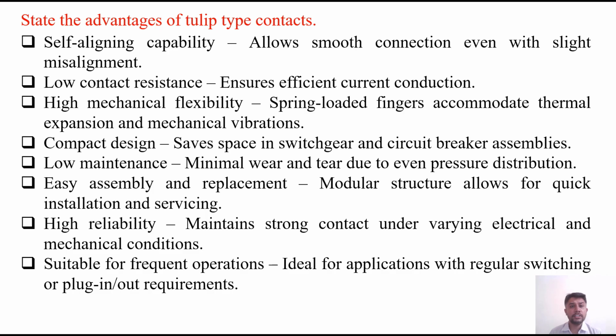State the advantages of tulip type contacts. There are several advantages of tulip type contacts, some of which are listed here. First is self-aligning capability. It allows smooth connection even with slight misalignment, because the male and female contacts fit like this, so it can allow smooth connection. Low contact resistance. It ensures efficient current conduction because the moving male contacts are fixed in the female contact. So it ensures low contact resistance because the contact area is very high.